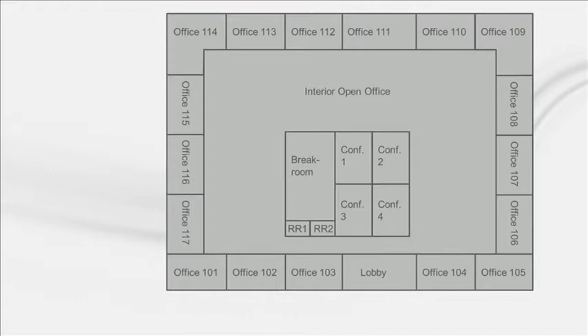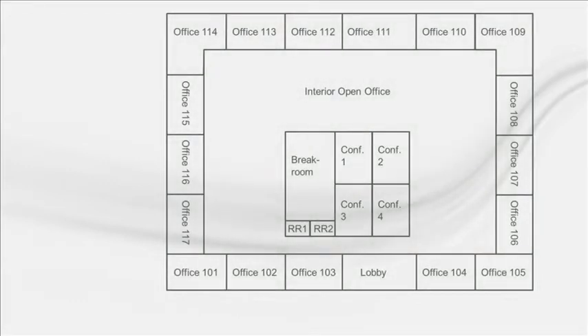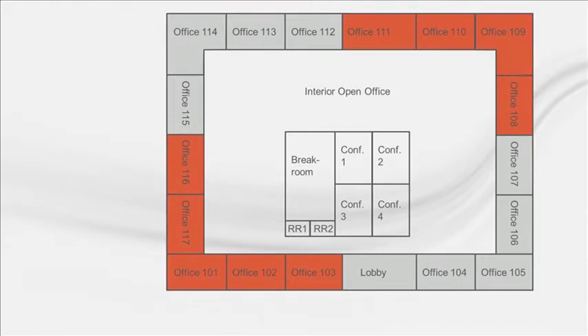We'll need at least 2 systems. So we can split the building into a couple of systems like I showed earlier. Based upon the building's location and loads, the building will probably require 3 or 4 systems. I might group the corners together to take advantage of heat recovery opportunities. I could put the zones on the northwest and southeast together and the northeast and southwest together.